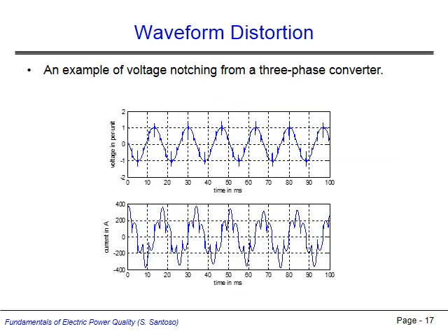This figure shows an example of voltage notching caused by a three-phase converter. As can be seen, brief fluctuations in voltage occur at regular intervals, six times per cycle. Each notch corresponds with the switching operation of the three-phase power converter.